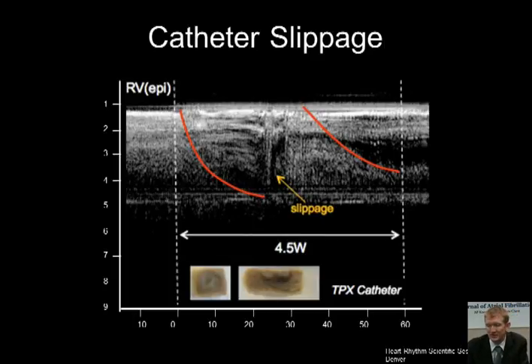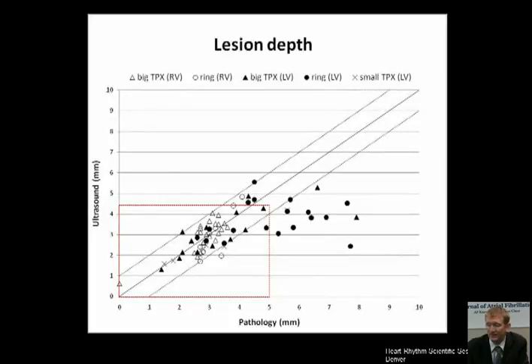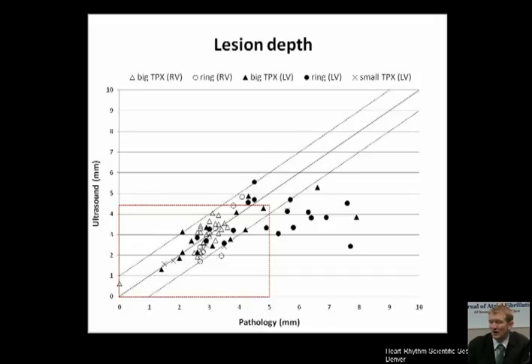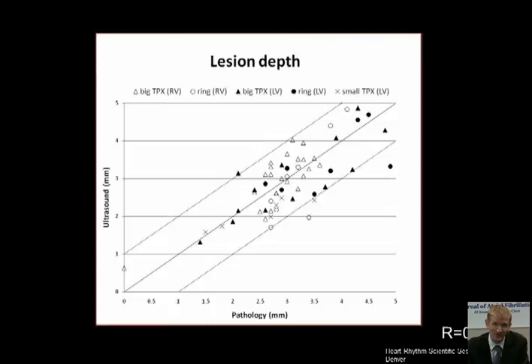Here are the results from the 112 lesions. There is very good correlation up to 5 mm. Beyond 5 mm, the resolution decreases and the correlation is not as good. On this graph, the 95% confidence limits are shown with the two dashed lines. For atrial fibrillation ablation, left atrium thickness is around 2 to 3 mm for most of the posterior wall, so the 5 mm depth of penetration is adequate. The R value is 0.78. We are working on further ways to improve this technology to go beyond 5 mm.